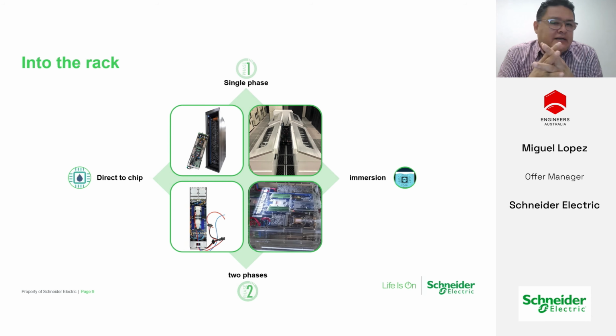There are, however, customers and applications requiring a so-called two-phase medium or fluid. Two-phase refers to a refrigerant which has the ability to boil as it absorbs the heat of the AI GPU or CPU, allowing that gaseous-liquid mixture to come back to the cooling distribution unit, which has a heat exchanger. In its attempt to remove that heat and give it up to the facility water system, it will then condense that gas to a liquid and recirculate the water back to and from the cold plates.